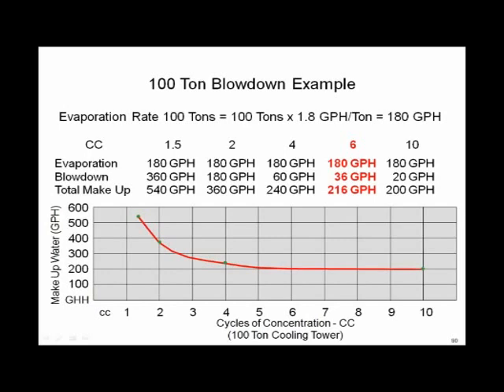All the way out to 10 cycles of concentration, evaporation rate is still 180 gallons per hour. The blowdown is down to 20. So I really have a lot of rocks. I'm at 10 cycles of concentration, up to 10 rocks. What are you seeing? The total water usage is flattening out. The amount of water you save by increasing the cycles of concentration goes way down as you increase it. In other words, going from 2 to 4, you save a lot of water. Going from 4 to 10, you save very little water.